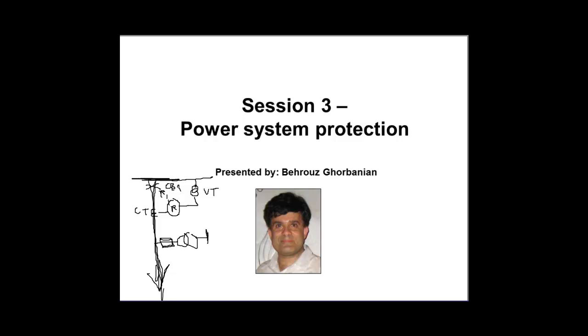Relay is more accurate. But sometimes, put it this way - what would happen if I lose this feeder? If you lose this feeder, okay, see that street? 20 houses will have an outage. That's one thing. What about if I lose this feeder? Well, I would say Trafalgar Square will have an outage. You tell me which one has got more severe damage here.